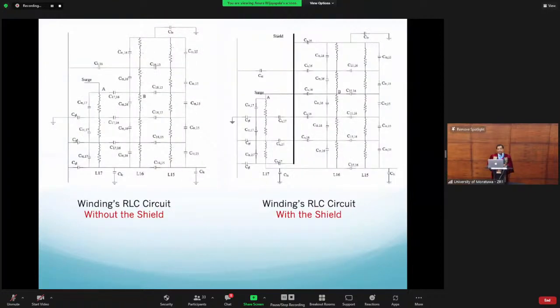We modeled two circuits with and without the shield for a 160 kVA transformer using data from Lanka Transformers Limited. You can see the shield in the winding, the black layer, and accordingly the capacitance to ground (CG) and capacitance to the winding (CF).